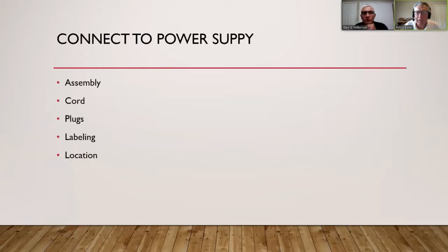But you get to some of the smaller units and they only have a 30 amp 120 volt. And now you go to a site and it has a 50 amp 250 volt. What do you do? Well, NEMA satisfied that requirement by making these little conversion cords. They're only about 12 inches long or 2 foot long, and it'll have the female receptacle for your male cord, like a 30 amp 120 volt. And it'll have a 50 amp male cap, so you can plug into that 50 amp source.